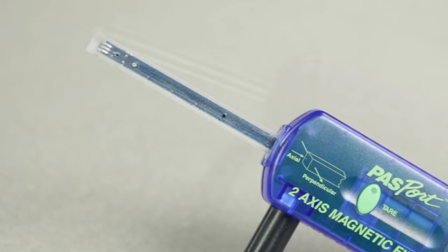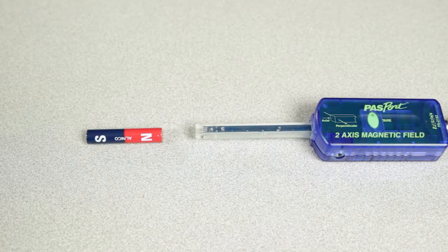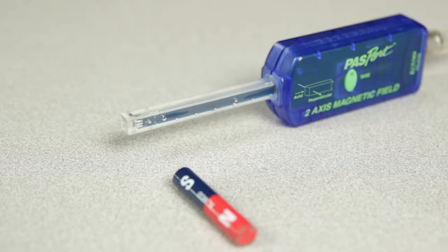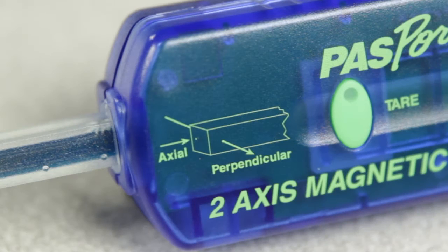Two perpendicular Hall effect devices at the end of the sensor's probe are used to measure the component magnitude of magnetic field strength in the axial and perpendicular directions as illustrated in the diagram printed on the sensor case.